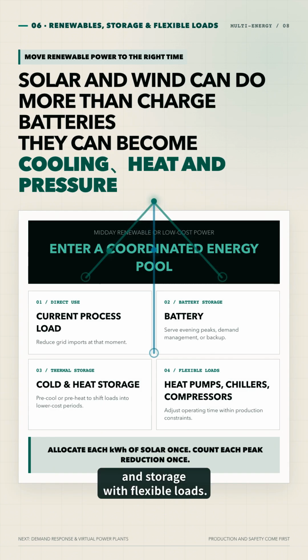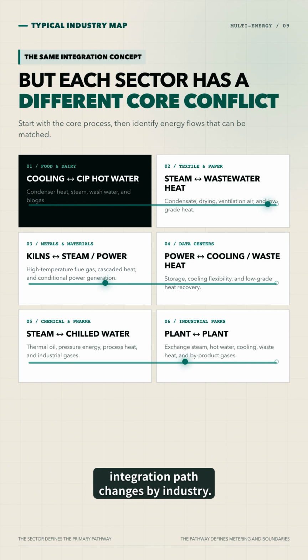The sixth type connects renewables and storage with flexible loads. Solar and wind power can supply production directly, charge batteries, or be converted into cooling, heat, or compressed air and stored in chilled water tanks, hot water tanks, or existing air receivers. Cooling, heating, and charging can be advanced into low-price or renewable surplus periods, reducing grid demand during the evening peak. Add production scheduling, interruptible loads, and demand response, and the result becomes coordinated dispatch across an industrial park. It may then connect to a virtual power plant. The same anti-double counting rule applies. 1 kilowatt-hour of solar generation can only be allocated once. The same peak reduction cannot be claimed in full by the battery, thermal storage, compressed air storage, and production shifting at the same time.